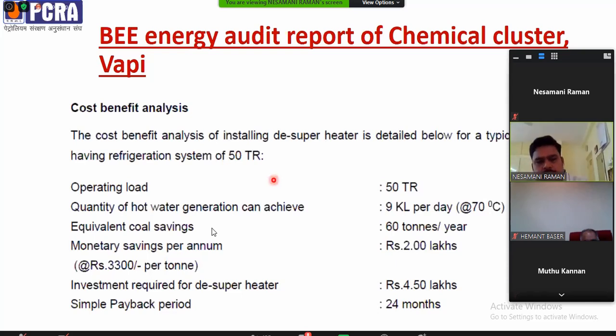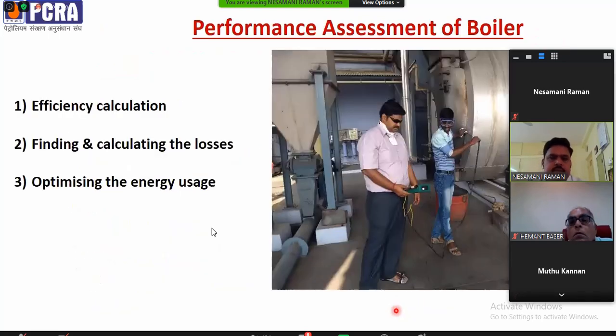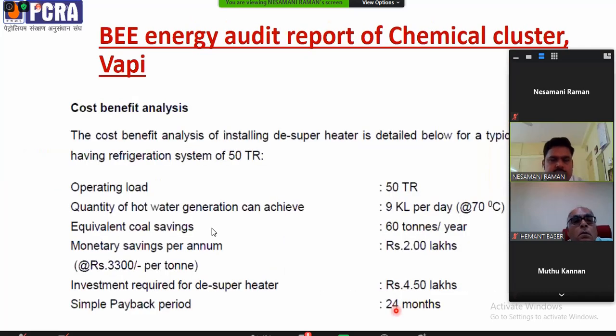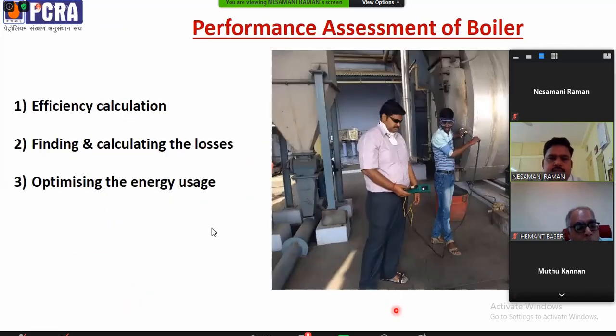For the monetary savings, they said that this hot water will be given to the boiler as feed water. Per annum they could achieve fuel savings of 2 lakhs. The payback period is almost 24 months. So this is about the desuperheaters in the chiller.